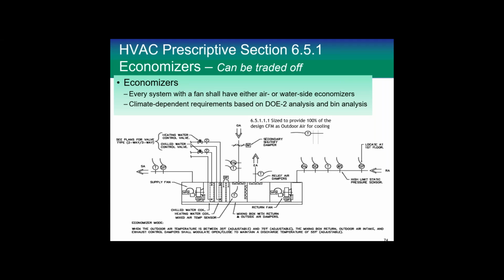Okay, so the requirement says that you have to size the outside air duct to handle the same amount of CFM as you're providing. So 100% of the CFM must be available to the economizer, and the duct must not be more restricted. Control off of the supply air temperature, not the mixed air temperature. So we want to control the economizer off the same thing that you're controlling the compressor off of. If you're controlling the compressor off the room thermostat, we want to control the economizer off the room thermostat. If you're using a VAV system where you're using the supply air temperature in the duct, we want to control the economizer off the supply air temperature in the duct. Now, both outdoor air and return air dampers shall meet the leakage requirements of the table for the normal louvers type dampers.